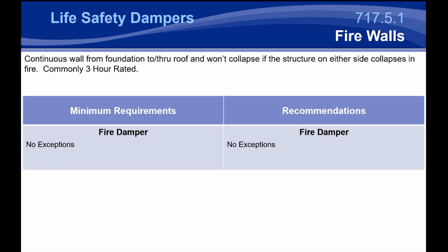Getting into the bulk of the presentation, I'm going to talk a little bit about different fire barriers, firewalls, and protective devices, going from most restrictive down to least restrictive. And then we'll talk about some different things at the end, like through penetrations going from one story to another. When we're talking about penetrating firewalls, it's not very common, but the code does require any firewall penetration to have a fire damper protecting it. There really aren't any exceptions.